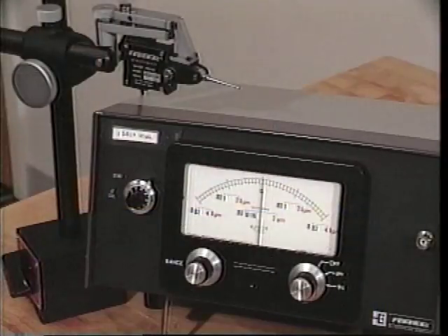Another high-resolution, small displacement measuring instrument is the electronic indicator gauge. This lever-type indicator gauge converts displacements of the stylus into voltages via a shaded pole inductor circuit. This particular instrument offers resolution down to plus or minus 1 microinch. Measurement linearity is 0.1%. While this instrument's measurement range of plus or minus 0.01 inches is an extremely attractive feature, its low frequency response of 300 Hz precludes its use in dynamic measurements.